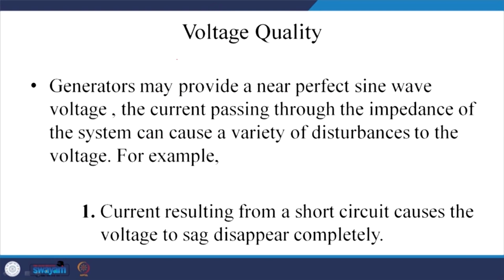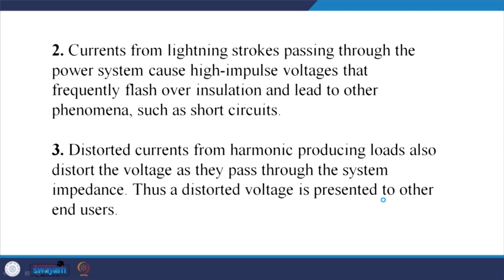So, what is the voltage part of the power quality? The generator may provide a near perfect sine wave voltage, very close to a sine wave. The current passing through the impedance of the system can cause a variety of disturbances in the voltage. For example, current resulting from a short circuit can cause a voltage sag, even disappearing completely. Current from lightning strokes passing through the power system causes high voltage impulses that frequently flash over the insulation and lead to other phenomena such as short circuit or trip of the breaker.